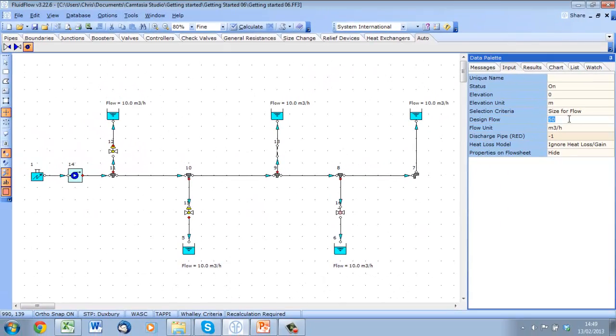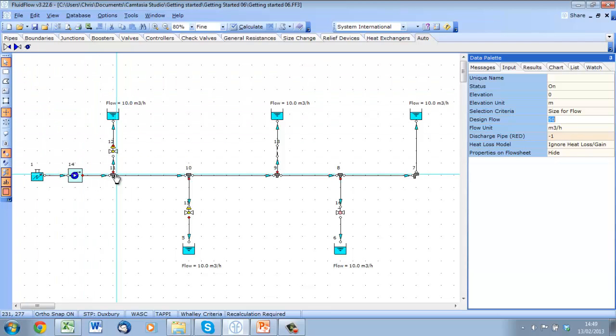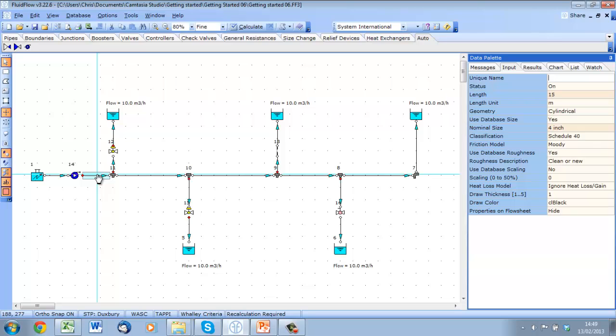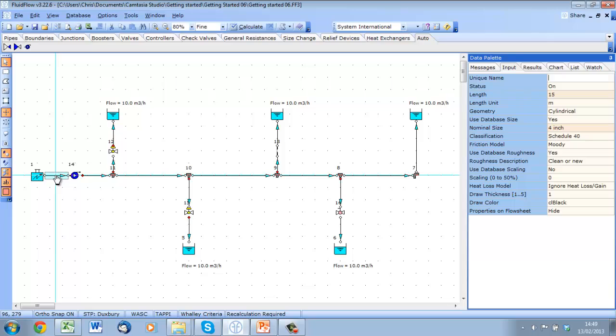We need to be careful though because previously we had only modeled the discharge pipe. By dropping the booster component on this pipe, we have split the length of it in half. So to rectify, let's set the discharge pipe back to 30 meters, and set the suction pipe to 3 meters, assuming that the pump station is adjacent to the tank.